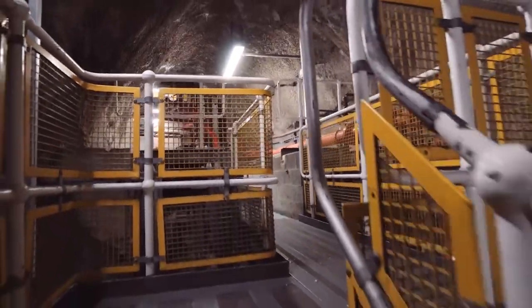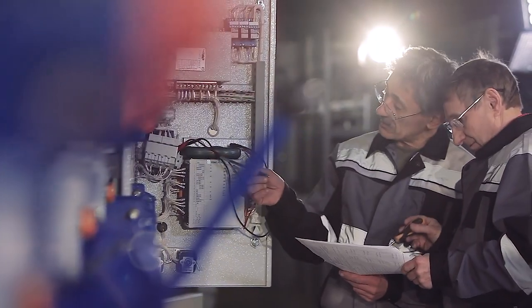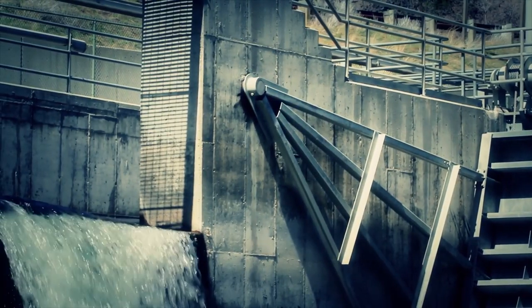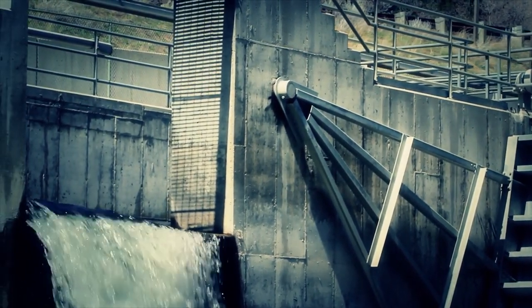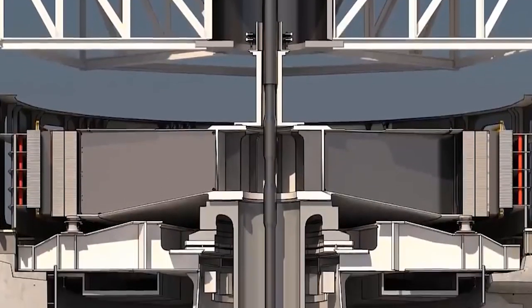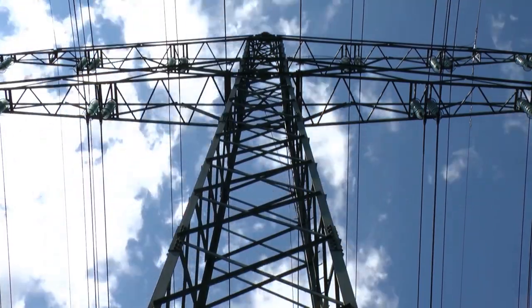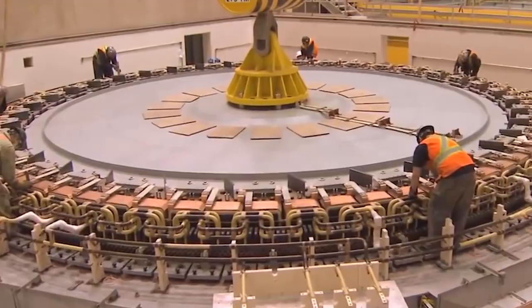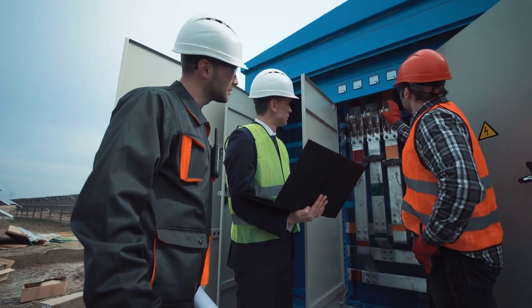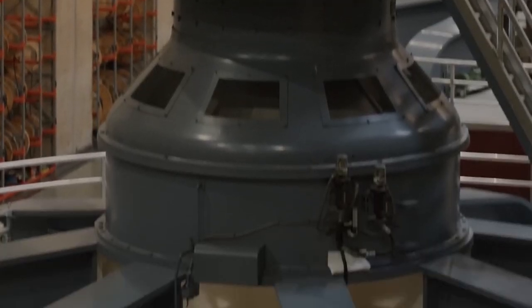You can feel the ground tremble as this valve opens, and the water presses down on it with a force of 29 atmospheres. The generation process creates an amazing force: the rotors inside the magnetic stators are driven to rotate at 500 revolutions per minute, producing 73 megawatts of power. These four generators can provide 292 megawatts of power when used collectively, capable of meeting around 4.8 percent of Ireland's peak electricity demand of 6,000 megawatts, which happens every day at around 5:30 p.m.